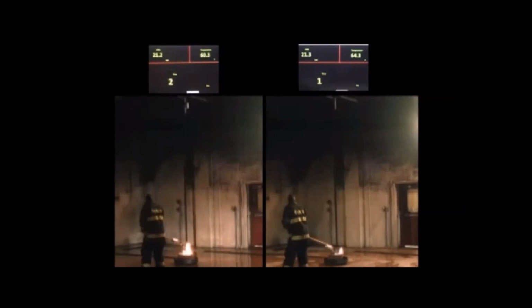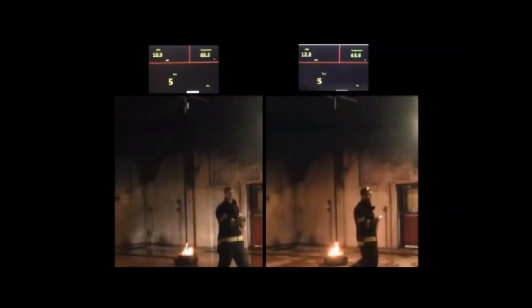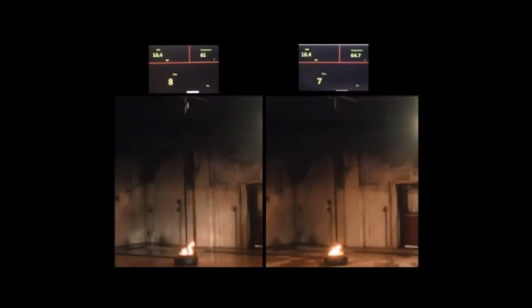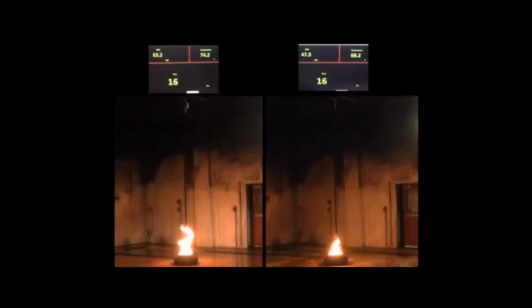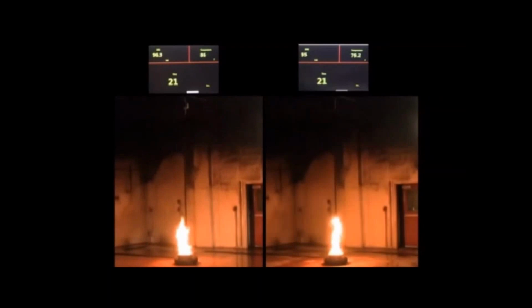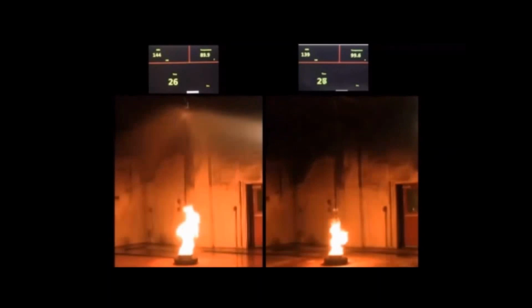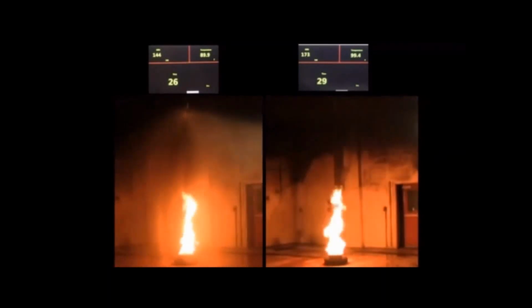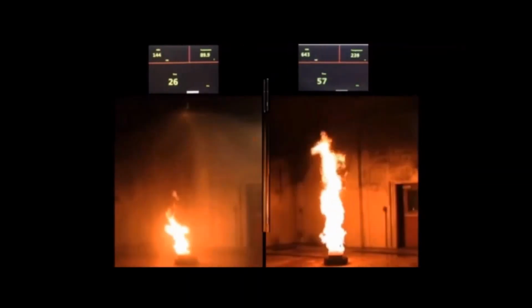So we have a video that's going to show the activation through electronics on the left-hand side versus the application where a thermal sensing element activates a sprinkler. It's pretty amazing to see the difference when you put in electronics. On the left-hand side, you're dealing with a rate of rise detection mechanism, and it's going to detect normally about a 20-degree temperature change from ambient. When it reaches that point, the thermal electronics tell that sprinkler to actuate. So in 26 seconds, we have actually actuated the sprinkler over this test pan.